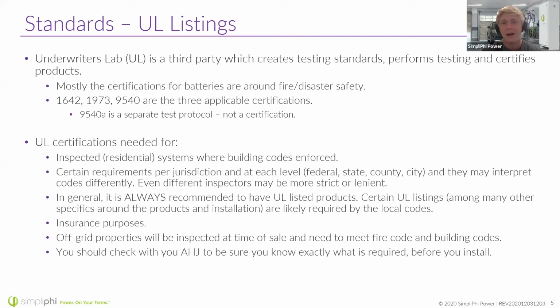In a lot of counties in California and New York, UL 9540 is completely required, meaning the inverter and batteries must both be UL listed and tested together for interoperability and compatibility. And 9540A is a growingly required UL certification that actually involves forcing the system into thermal runaway by adding external heat and seeing how it reacts.